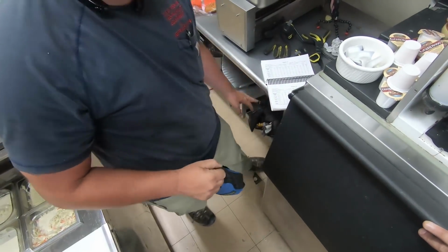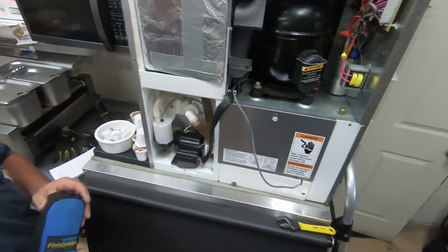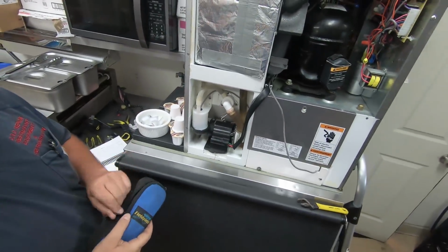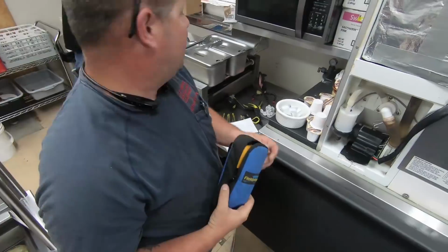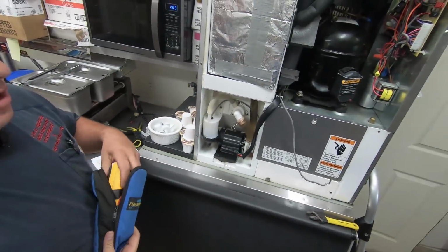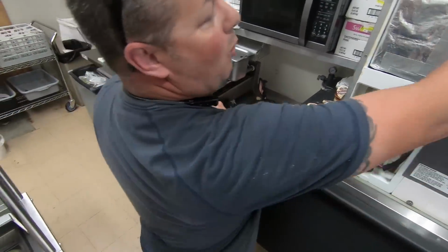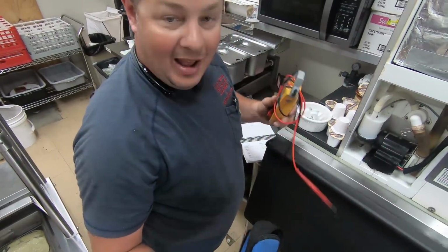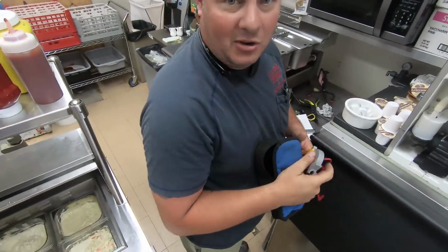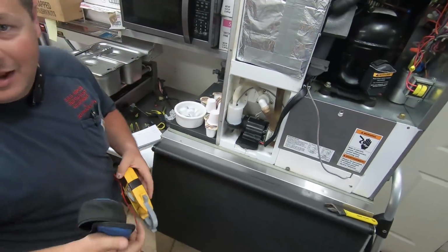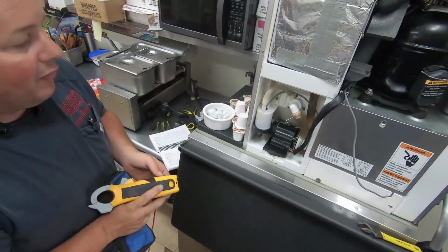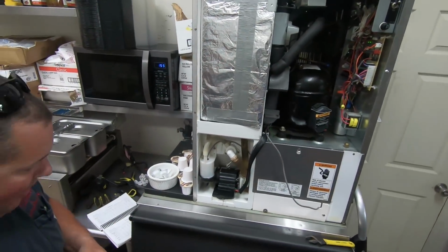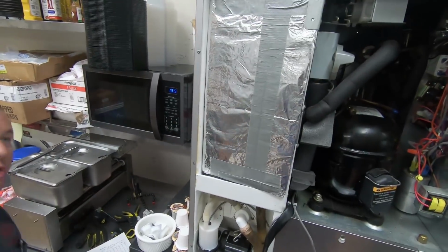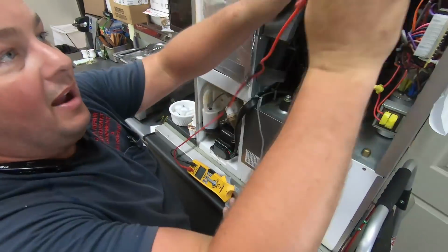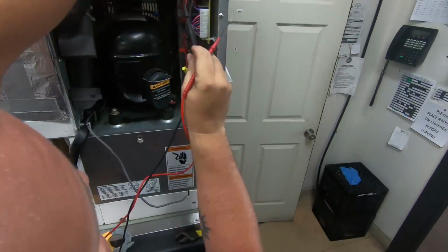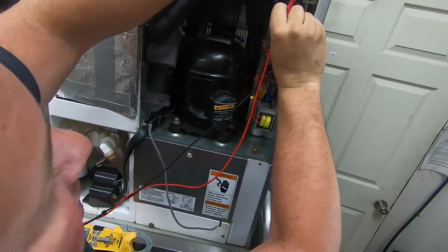This is all the controls. The board is low voltage internal to the board, but everything it switches is 115 volt, even though this is a 208 machine, right? All of our water valves, our solenoid for defrost, hot gas bypass or defrost, harvest valve, right, all of those are 115 volt. So I know my compressor is 208, but all my other functions are maybe 120 volt.